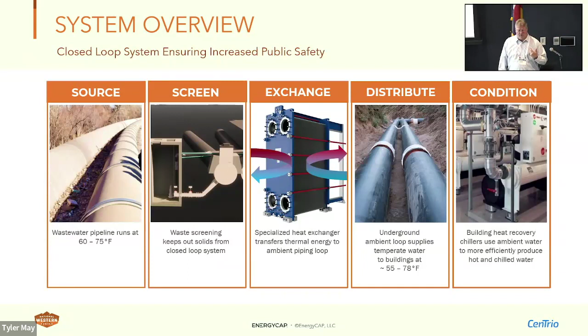And then at the end, the buildings have heat recovery chillers or heat pump type systems that, like I said, can work just like a typical ground-coupled heat pump you might have, or if you're using geothermal, same technology, but we're just using our ambient loop instead of pulling water out of the ground.